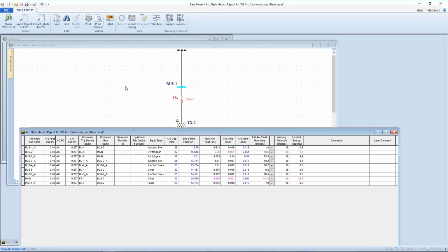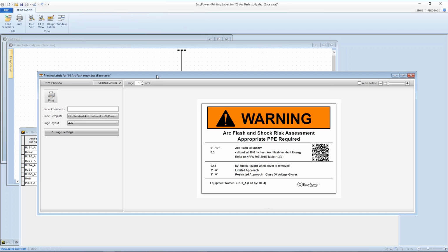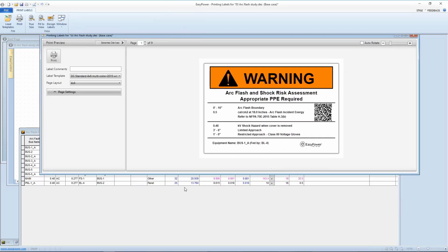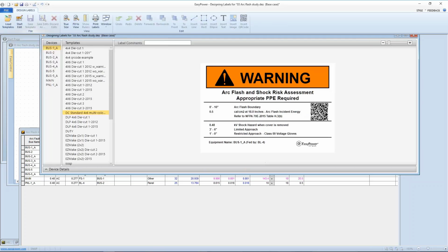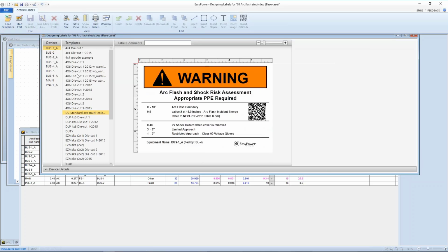I'm happy with the results of the short circuit, the equipment duty, the coordination report, and now my arc flash calculations. I'm ready to produce the labels. The tool has built into it a label editor, which will allow me to take the data from each of these indicated buses and apply them to a template. Again, there's 15 to 20 templates included with the tool. And if I wanted to make a modification, for instance, put my own logo or change the wording, I would use the built-in label editor.